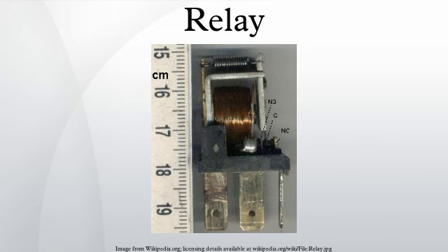If one set of contacts in the relay becomes immobilized, no other contact of the same relay will be able to move. The function of forced guided contacts is to enable the safety circuit to check the status of the relay.